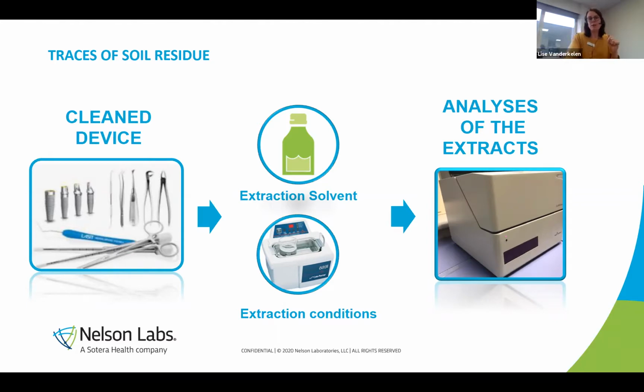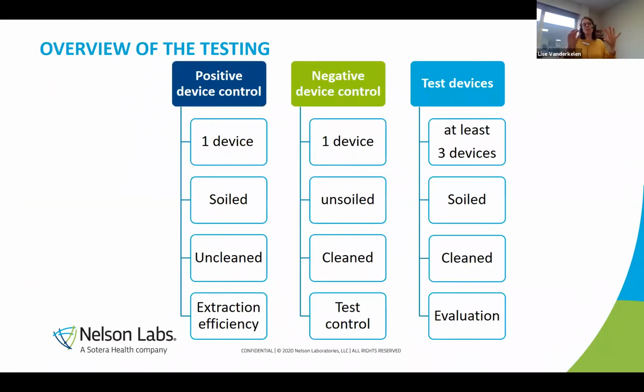During this step of the evaluation, we will take a positive and a negative device control into account. The positive device control is a device which is soiled, so it's very dirty, but it's not cleaned, and will be used to determine the extraction efficiency. I will come back to that in the next slide. The negative device control is one device which is unsoiled and cleaned and is used as a test control to see whether or not there is interference in our analytical testing, to make sure that everything is under control.